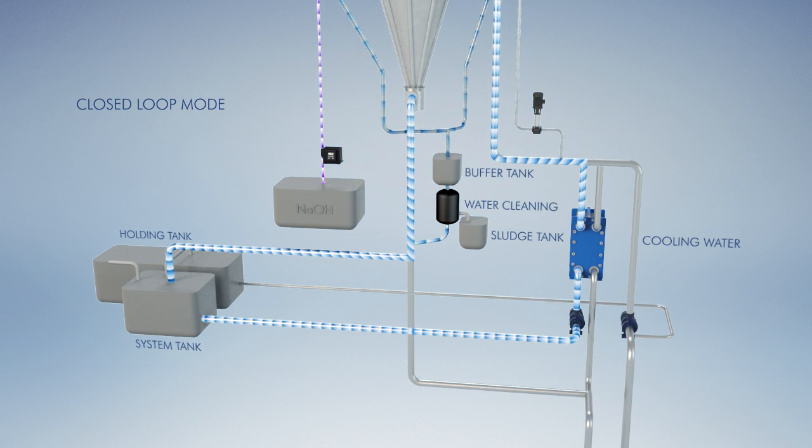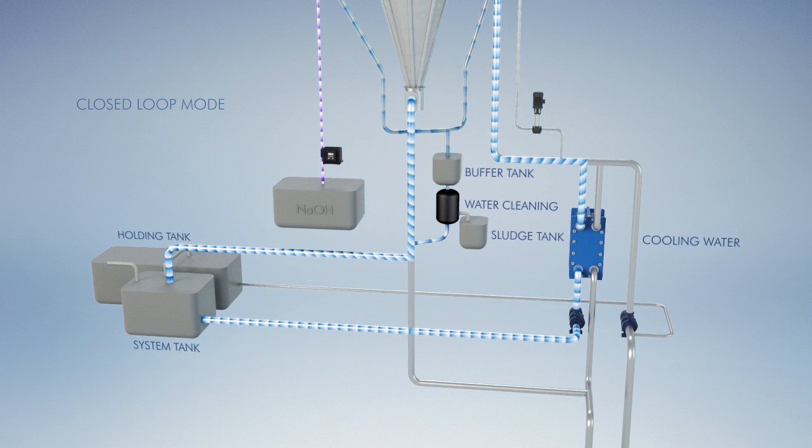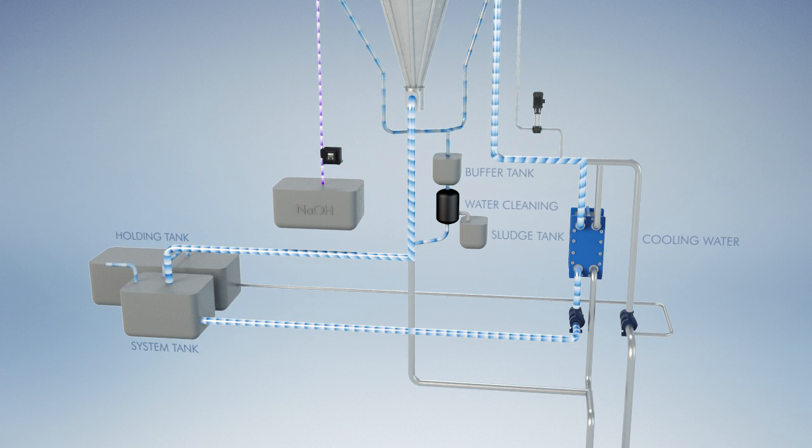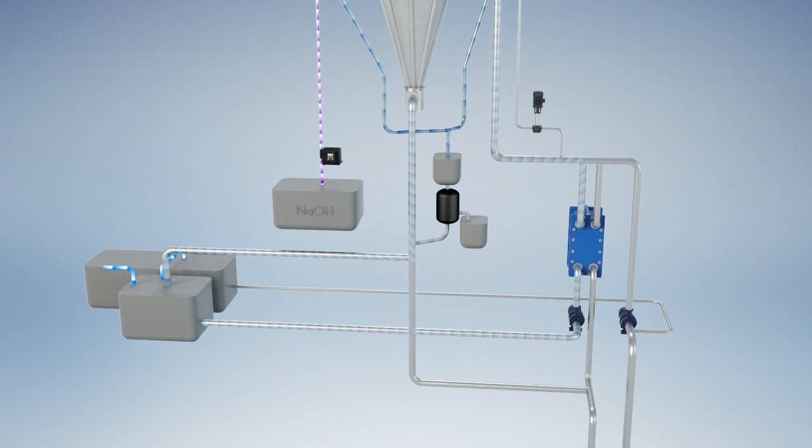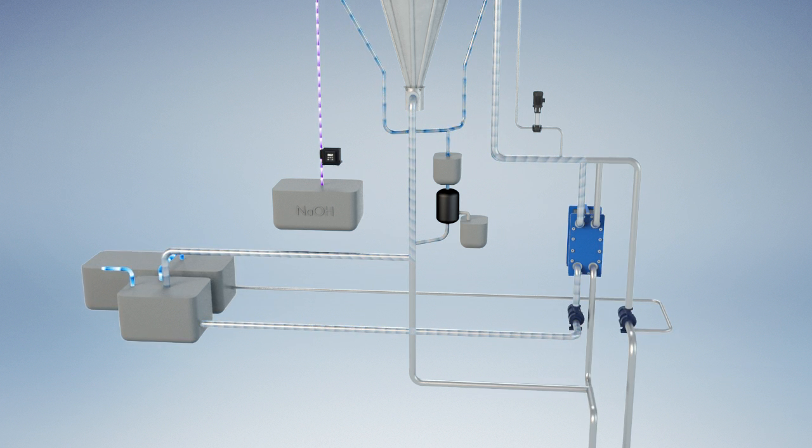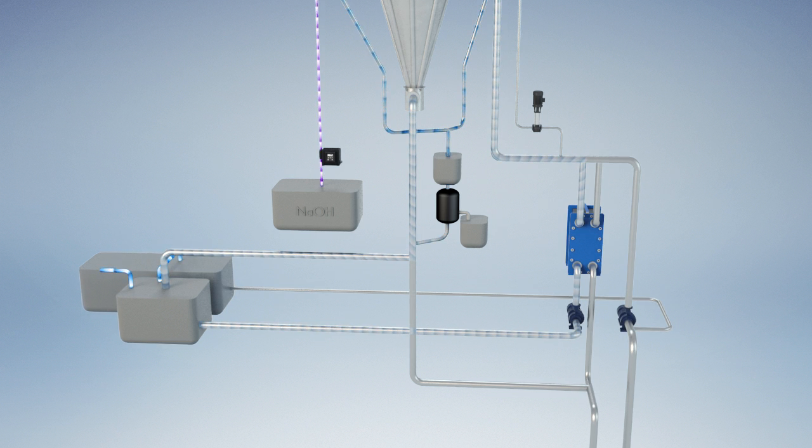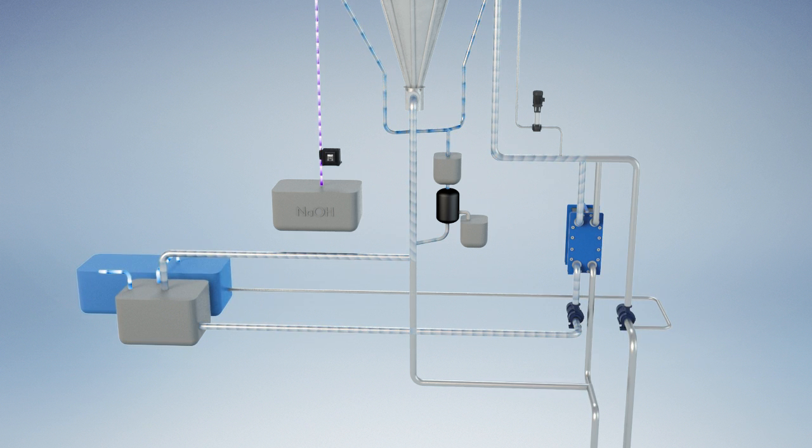The cleaning water dosed with caustic soda is then circulated through the system while a bleed and corresponding make-up stream ensures that saturation is avoided. The thoroughly cleansed bleed stream is led to a holding tank for later discharge to sea or ashore.